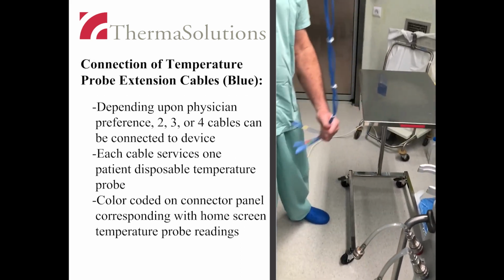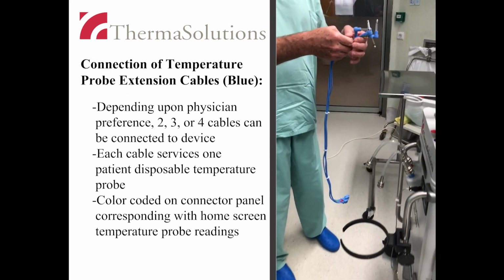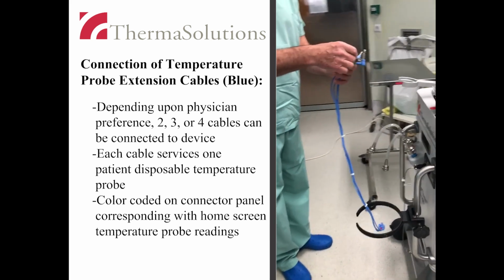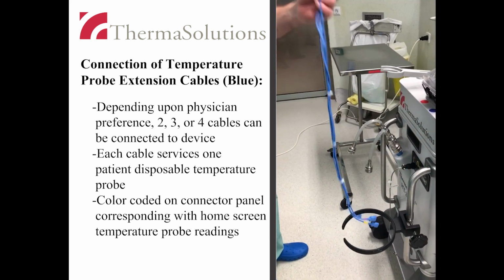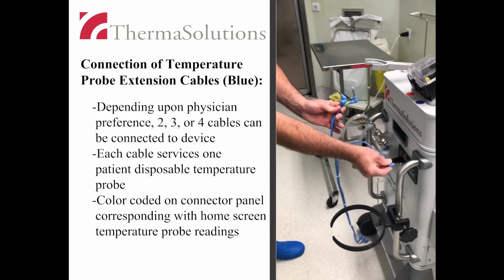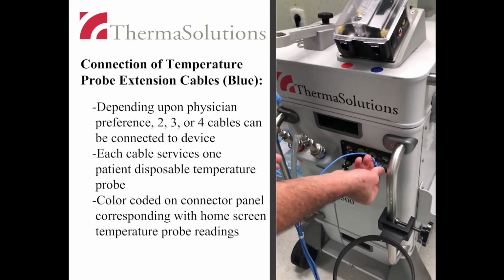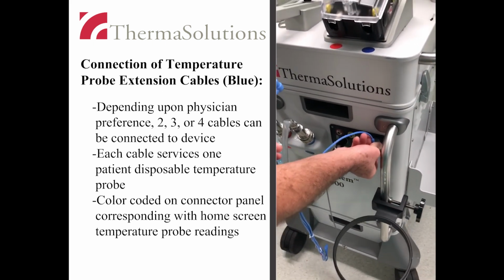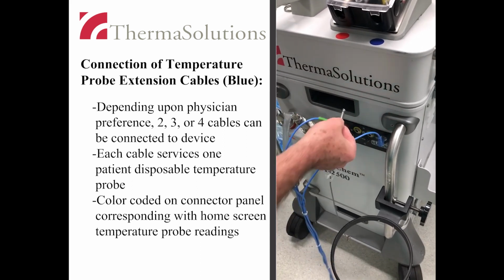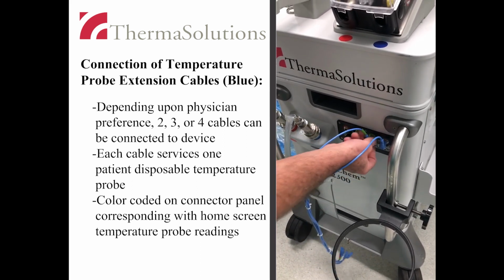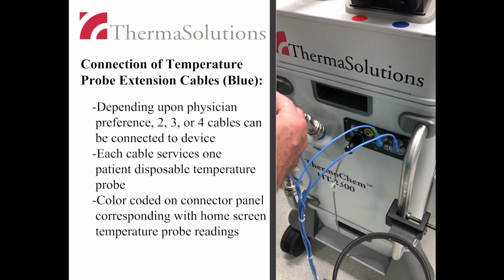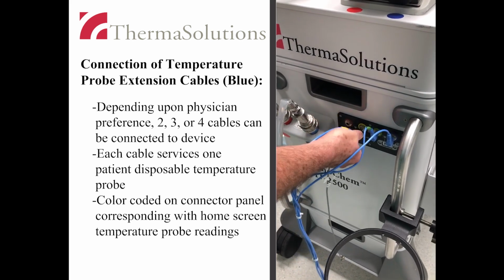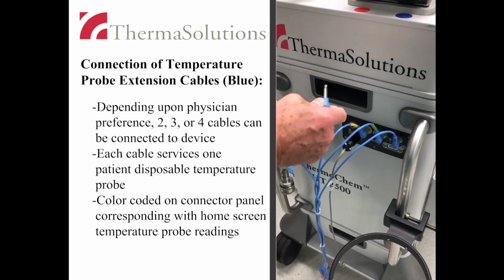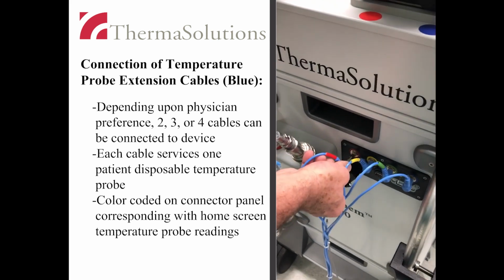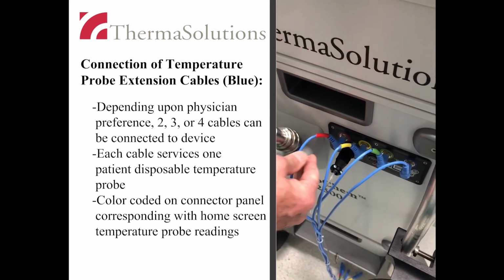Connect the blue temperature probe extension cables at the connector panel into the color-coded receptacles. Depending upon physician preference, 2, 3, or 4 cables can be connected to the device, and each cable will connect to a disposable patient temperature probe.